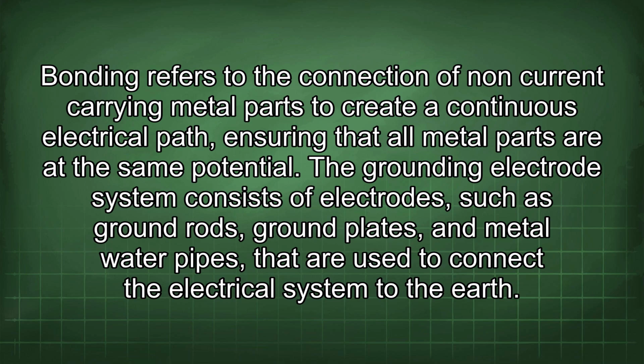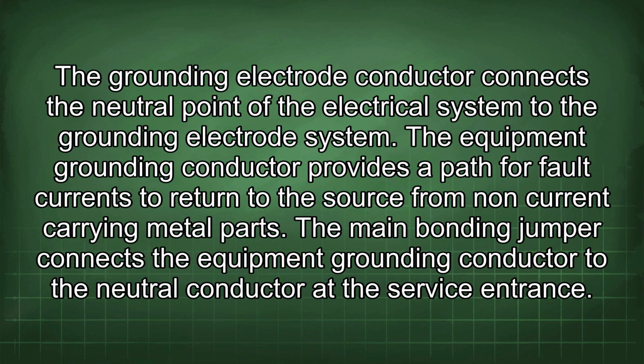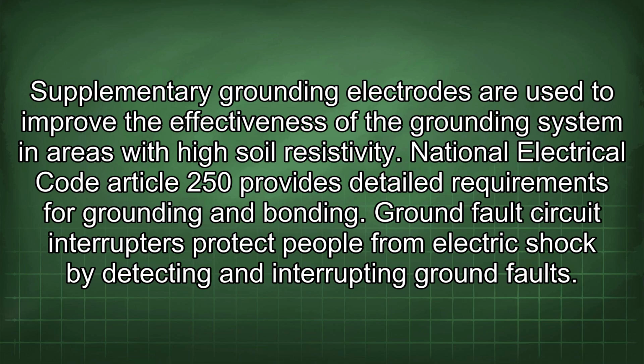The grounding electrode system consists of electrodes, such as ground rods, ground plates, and metal water pipes, that are used to connect the electrical system to the earth. The grounding electrode conductor connects the neutral point of the electrical system to the grounding electrode system. The equipment grounding conductor provides a path for fault currents to return to the source from non-current carrying metal parts. The main bonding jumper connects the equipment grounding conductor to the neutral conductor at the service entrance. Supplementary grounding electrodes are used to improve the effectiveness of the grounding system in areas with high soil resistivity. National Electrical Code Article 250 provides detailed requirements for grounding and bonding.